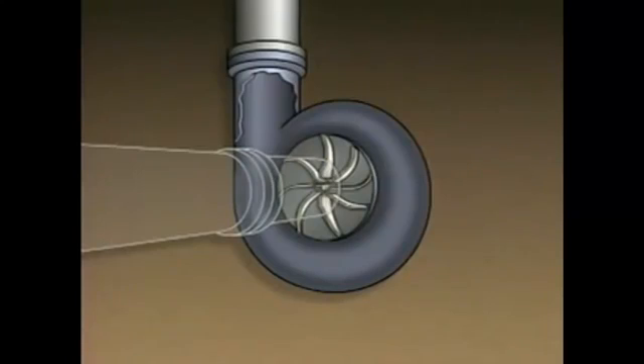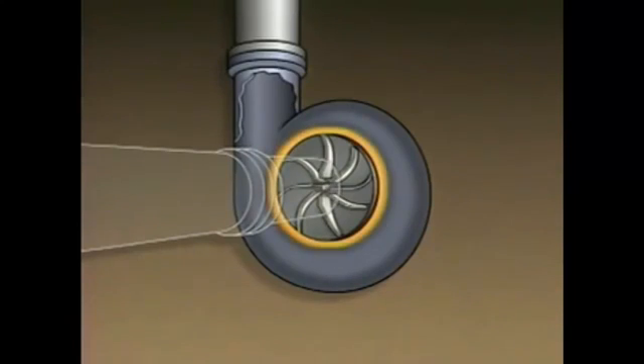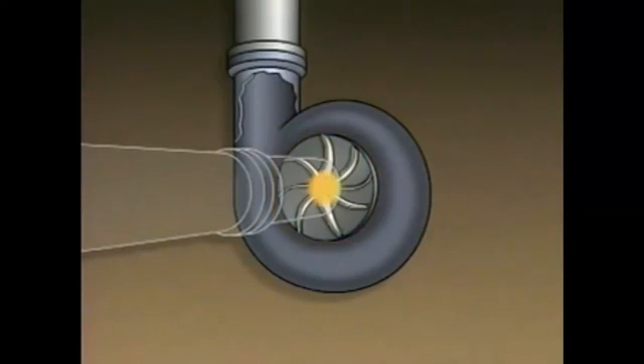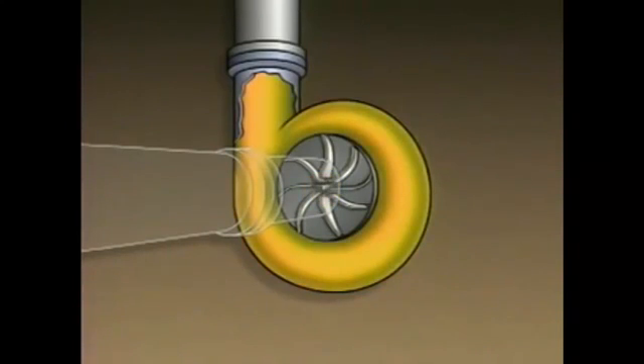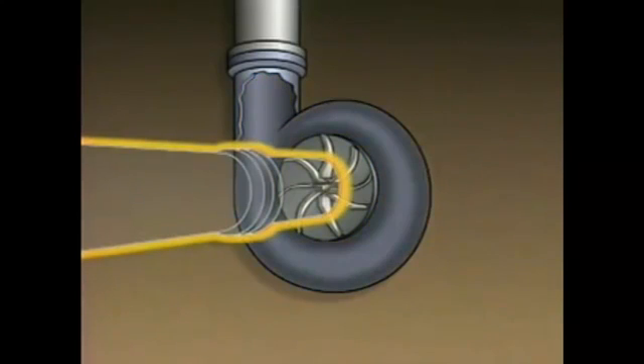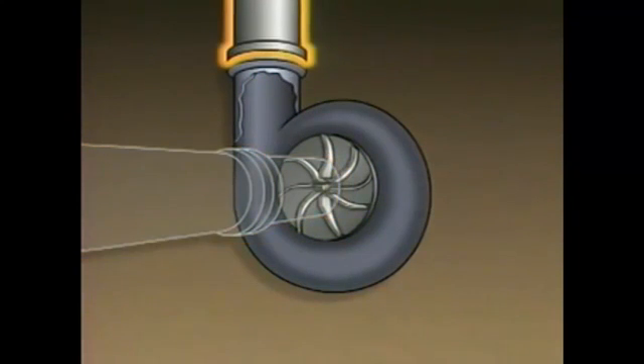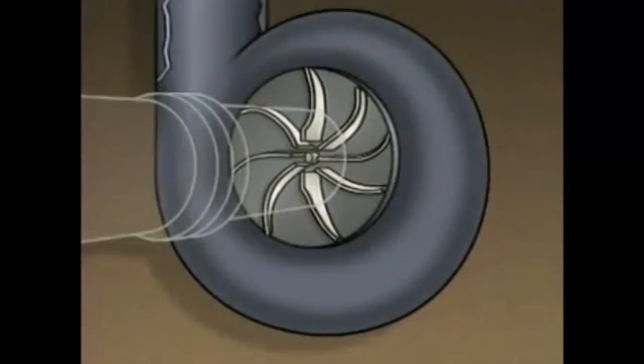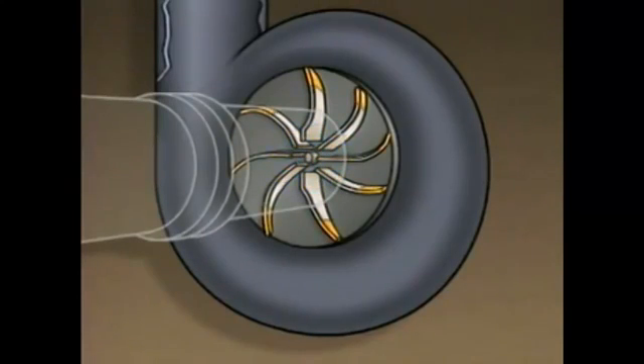Now let's look at a single-stage centrifugal compressor from the suction line side to see how it works. In this illustration, we can see the impeller, the suction eye, which is the area in the center of the impeller, the volute, the suction line, and the discharge line. The impeller consists of a series of vanes. The tips of the vanes closest to the shaft are called suction vane tips. The tips farthest from the shaft are called discharge vane tips.